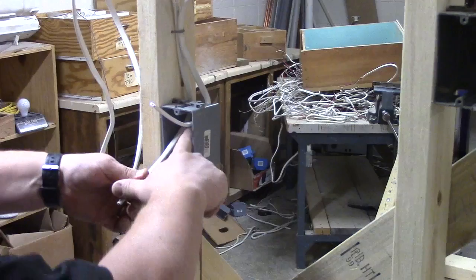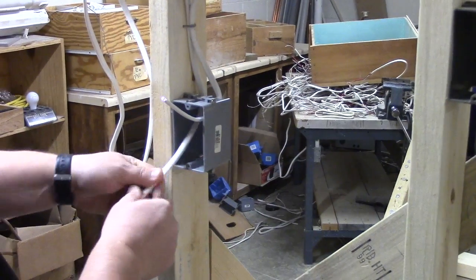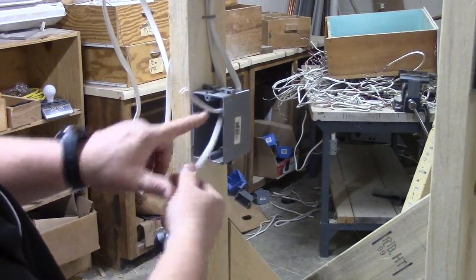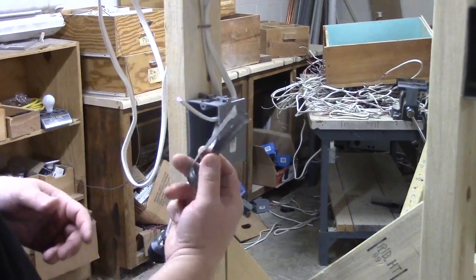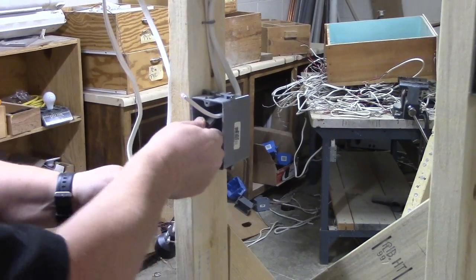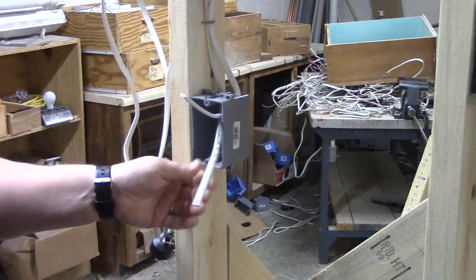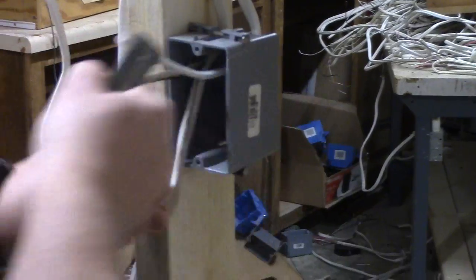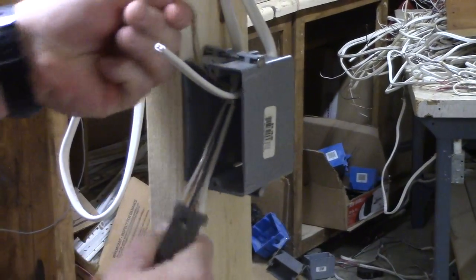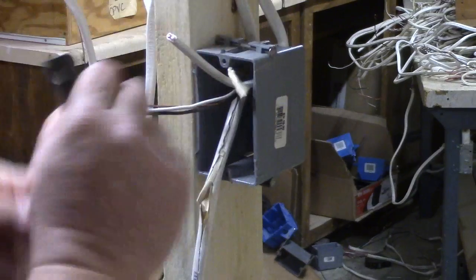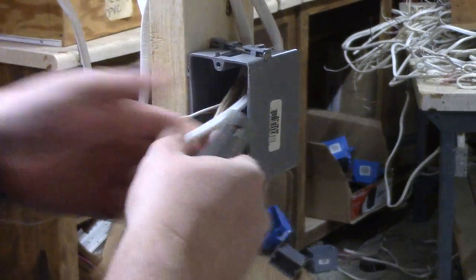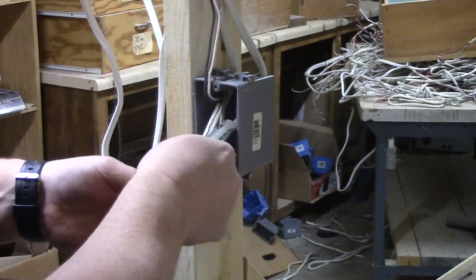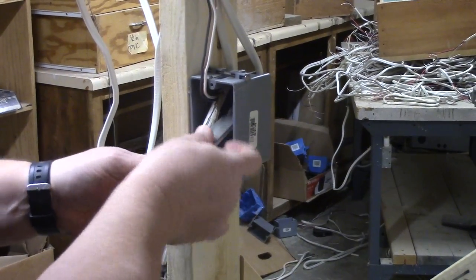Let's strip these back. I've got six to eight inches of wire in my box. An easy way to determine that - your finger from here to here is roughly six to eight inches depending on how big your hands are. I got a pair of rippers and I'm going to run them up in there, clamp down, pull it out. As you can see, it just tears it right off nice and neat. I got to remember which wire is which. This is my electricity coming in, so I'm going to fold it up.